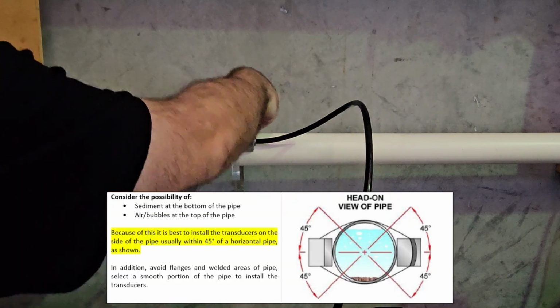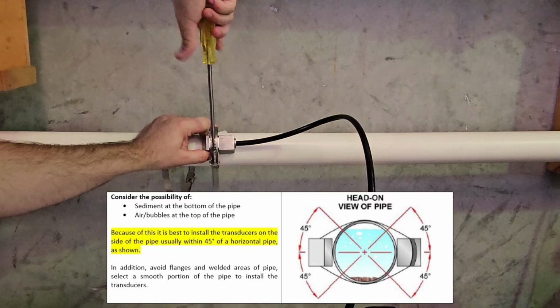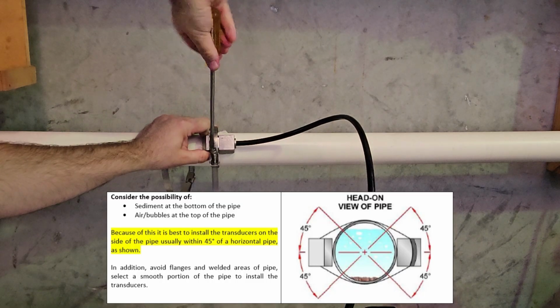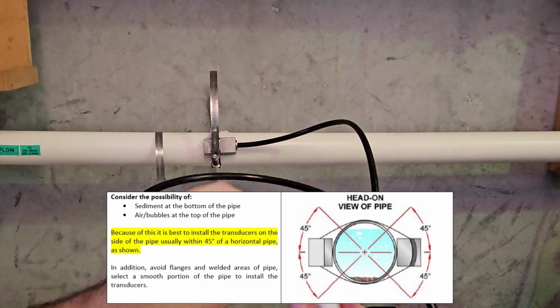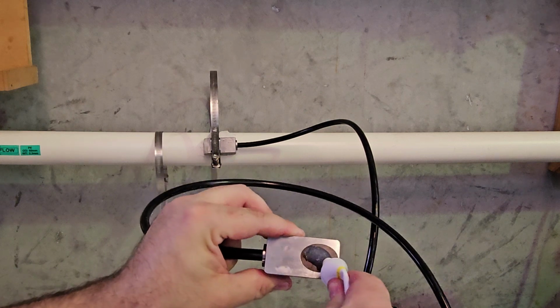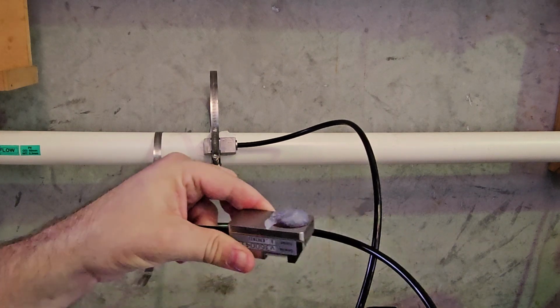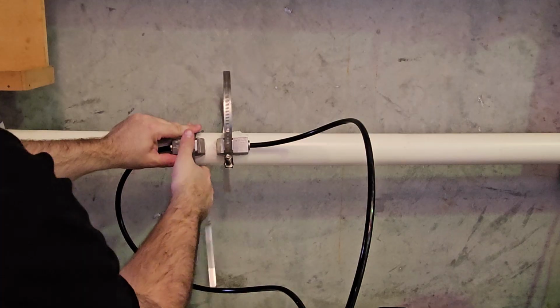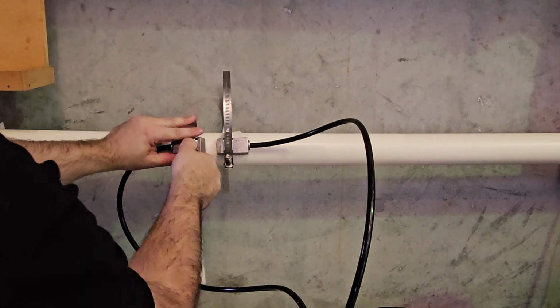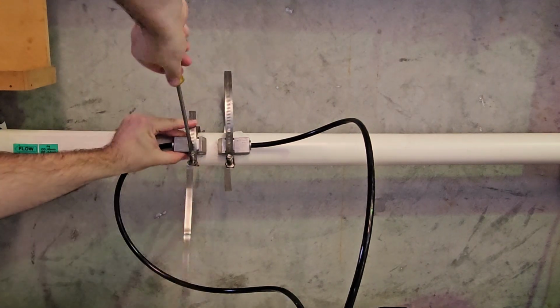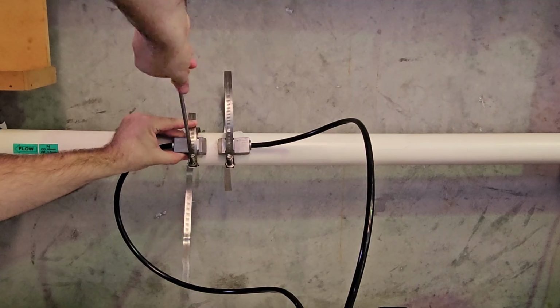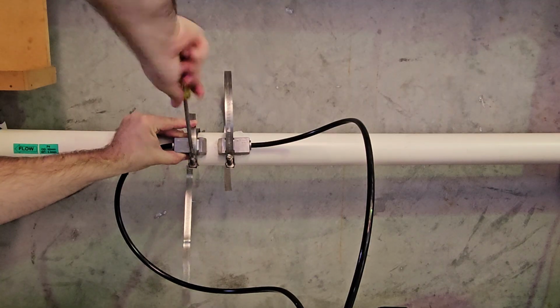It's suggested to mount the sensors on the side of the pipe as shown, to avoid sediment at the bottom and air bubbles at the top. Next, take the downstream sensor, checking the label and noting the flow direction. Add couplant and begin spacing the sensor on the pipe, remembering the total space needed between both sensors. Tighten down the pipe straps and start to align the sensors.